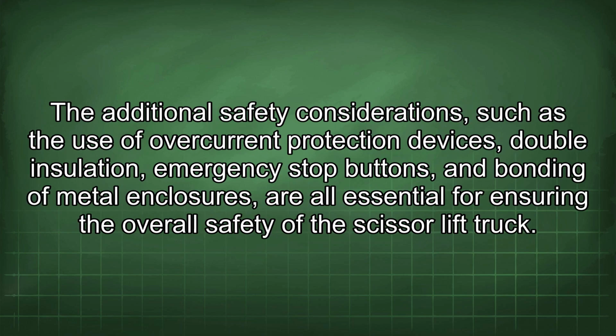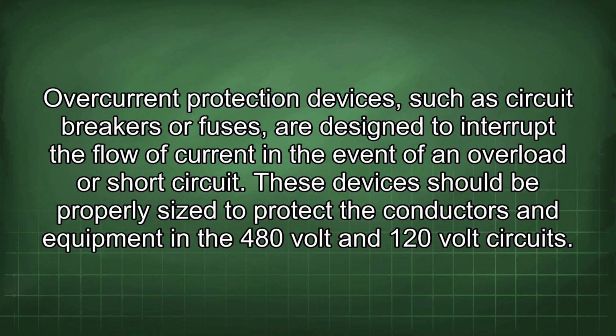The additional safety considerations, such as the use of overcurrent protection devices, double insulation, emergency stop buttons, and bonding of metal enclosures, are all essential for ensuring the overall safety of the scissor lift truck. Overcurrent protection devices, such as circuit breakers or fuses, are designed to interrupt the flow of current in the event of an overload or short circuit. These devices should be properly sized to protect the conductors and equipment in the 480-volt and 120-volt circuits.